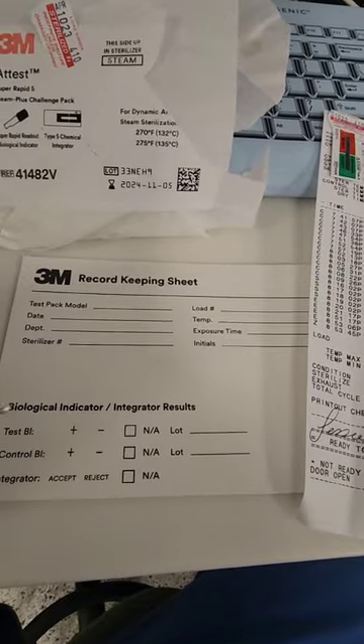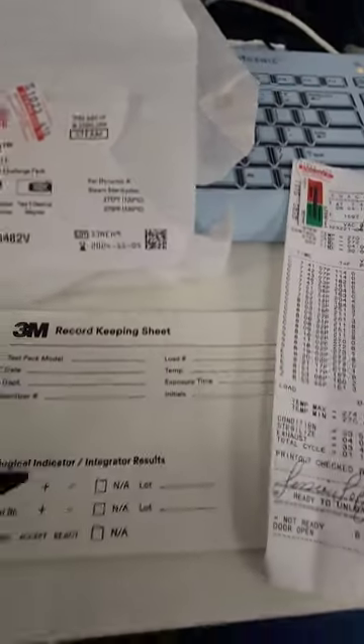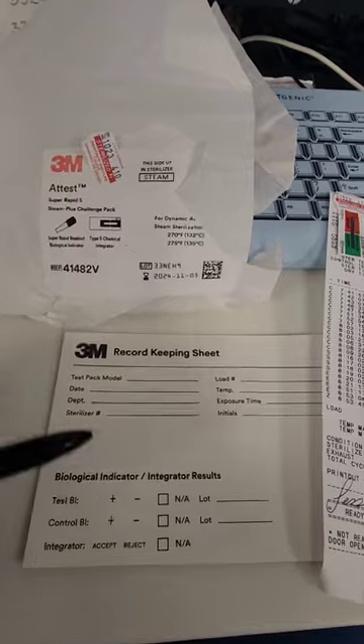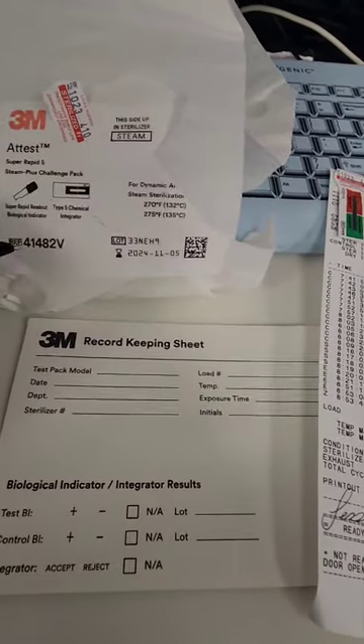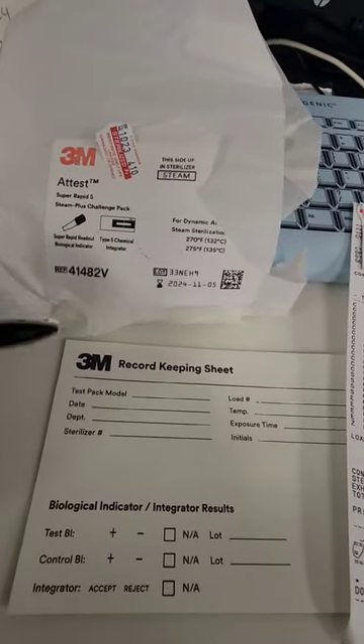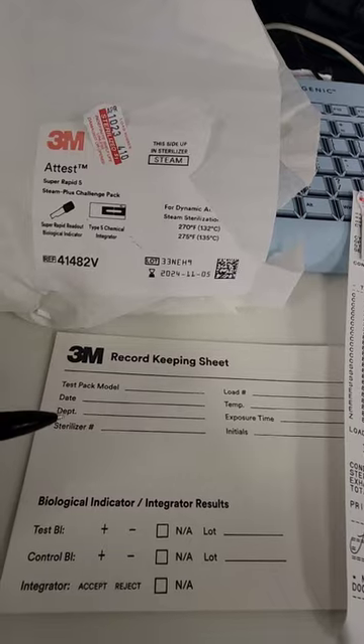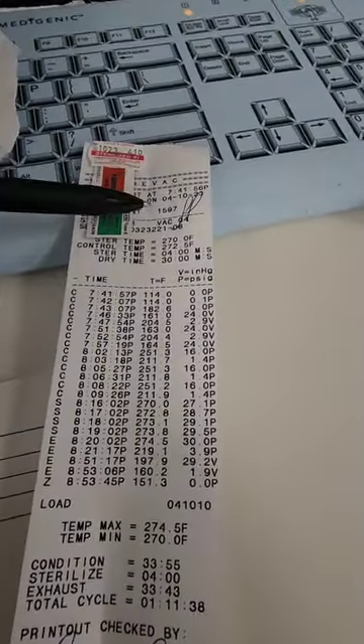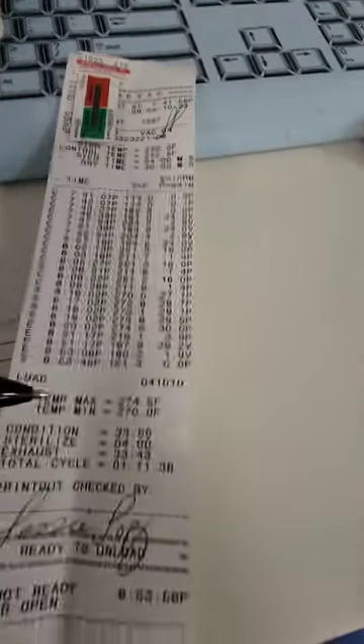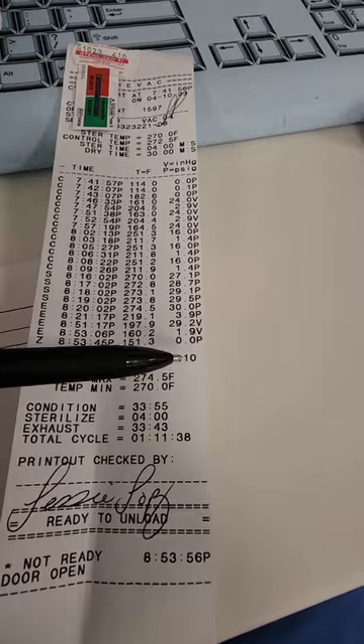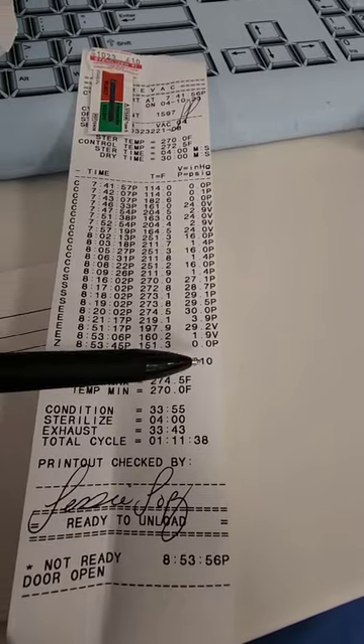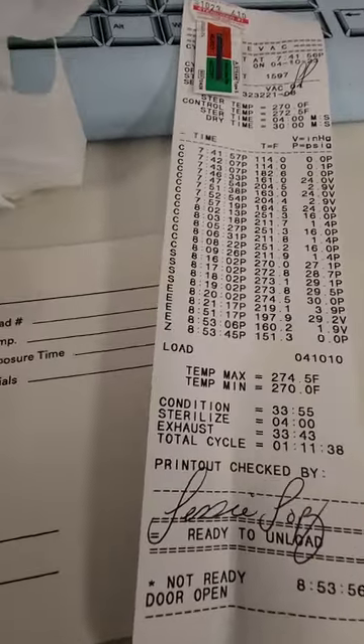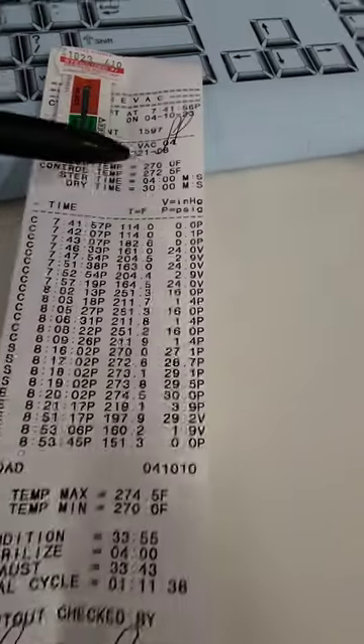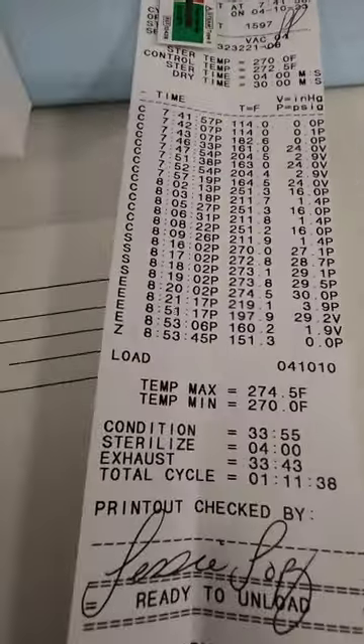Now I'm gonna show you how to do a manual copy. If you don't have an electronic system and you have to still use a manual process, it's no problem, pretty easy. So here's what's on the information it asks for. It asks you for the test pack number. It asks you for the date, the department, the sterilizer, what load you're gonna run. This is where the load's found, the last two digits or the last digit. It's gonna ask you the temperature and exposure that you ran. Okay, that's in your summary right there.